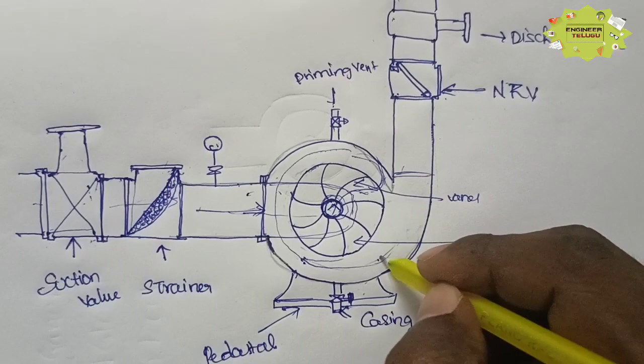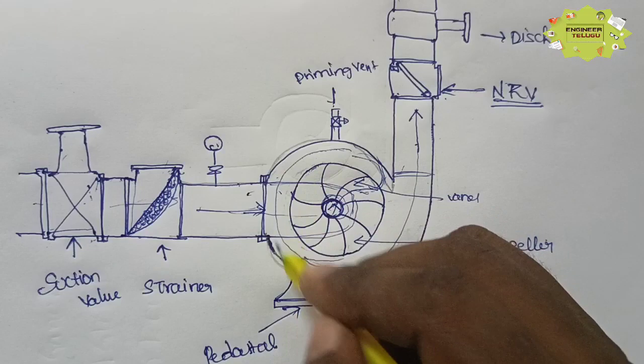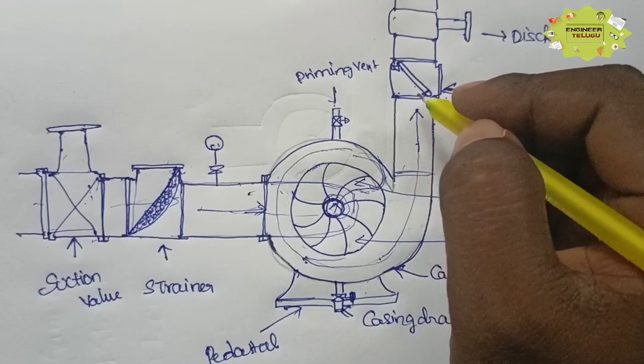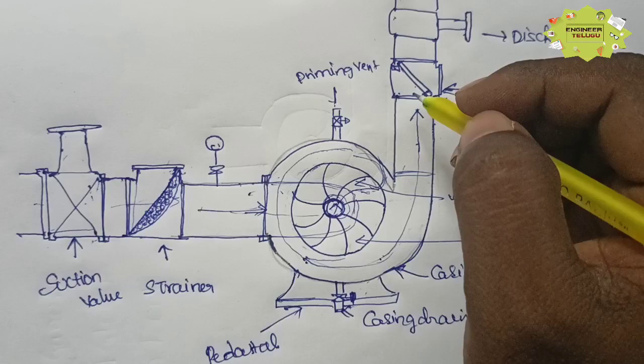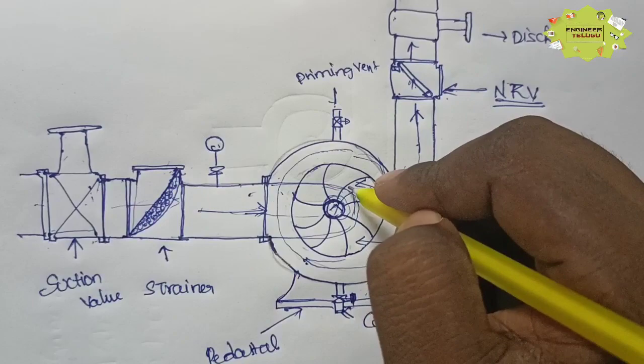This is the discharge. The discharge has an NRV — this is the non-return valve. When the pump is running and pressure builds up, flow passes through. The NRV closes when the pump stops, preventing backflow. This is the basic design of the pump flow path.